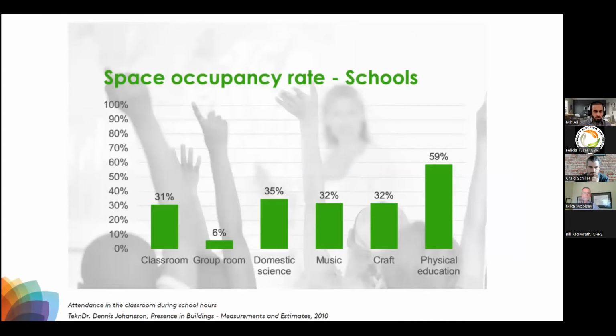From this graph, as I mentioned, classrooms only represent 31% occupancy rate, and when they are used, they are full, so they need a good amount of air supply. The best way to save energy is by having demand control ventilation to classrooms and other spaces. When there's no occupancy, we can cut or reduce the airflow and save energy.